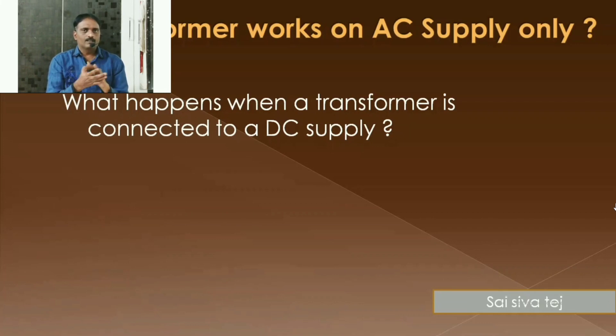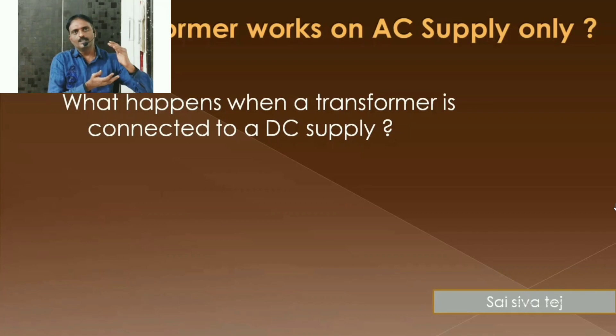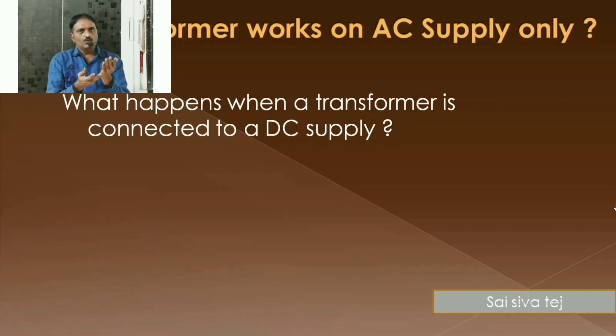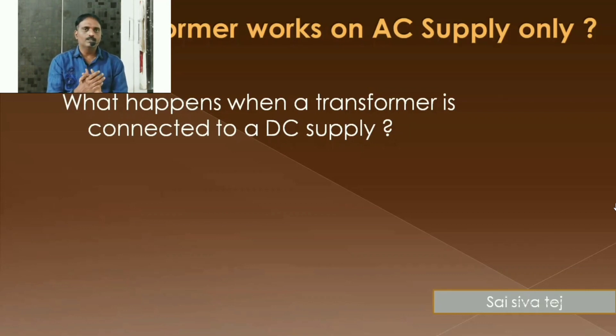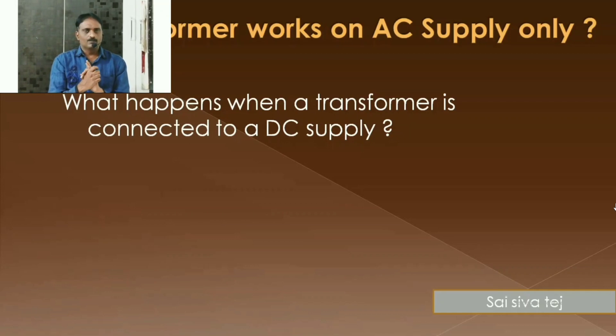That large current may damage the winding and the essential parts of the transformer. For example, say 200 volts of DC is given to the primary side and the primary winding has a resistance of 1 ohm. When we apply simply Ohm's law, I = V/R = 200/1 = 200 amperes, which is a very large current and there is a possibility that the winding may get damaged. So that is the reason why it is very important to remember that the transformer should not be given a DC supply. That is why it is simply an AC machine — a static device.